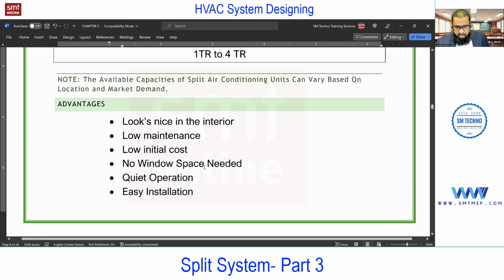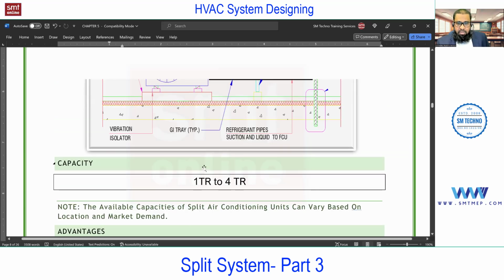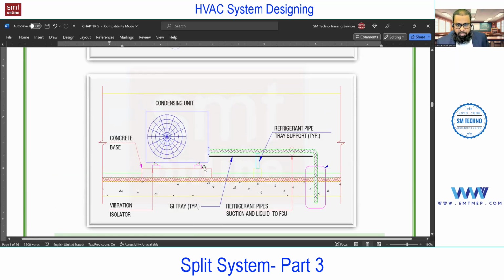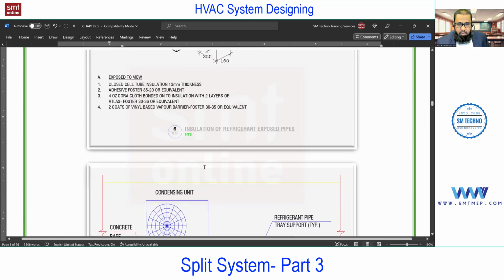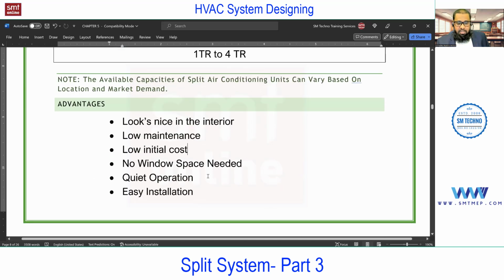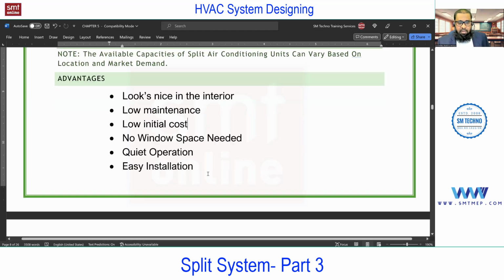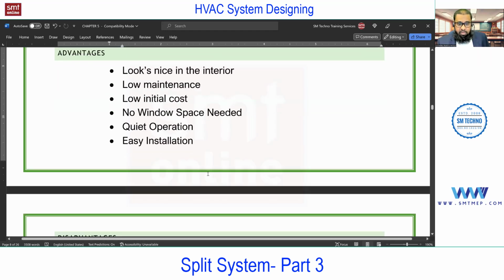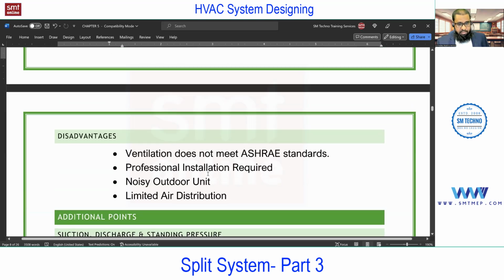Next, no window space needed, like window AC. For window AC, the opening is required. No? Without that, you cannot install. But this high wall, we can install on any wall in the room. It's not a must that it should be an exposed wall or have an opening. Next, easy installation. Again, easy installation not compared with the window, but compared with the other central types like ductable split or VRF, etc. Anyhow, a skilled technician is required for this, which you'll find in disadvantages.